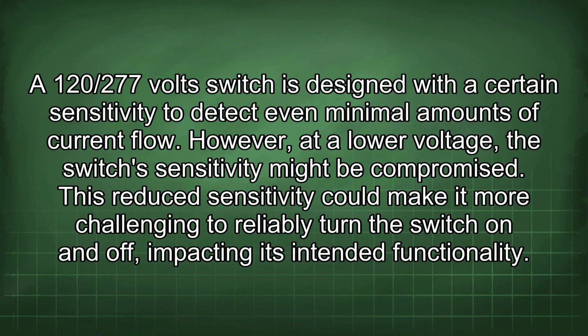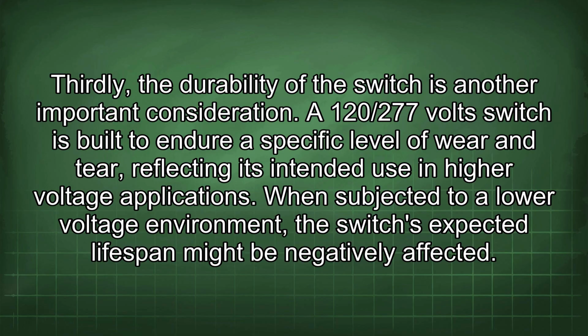However, at a lower voltage, the switch's sensitivity might be compromised. This reduced sensitivity could make it more challenging to reliably turn the switch on and off, impacting its intended functionality. Thirdly, the durability of the switch is another important consideration. A 120/277 volts switch is built to endure a specific level of wear and tear, reflecting its intended use in higher voltage applications. When subjected to a low voltage environment, the switch's expected lifespan might be negatively affected.